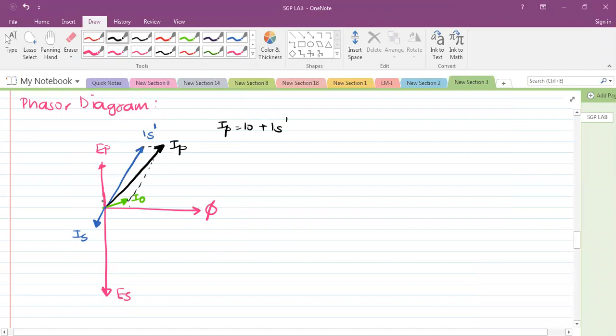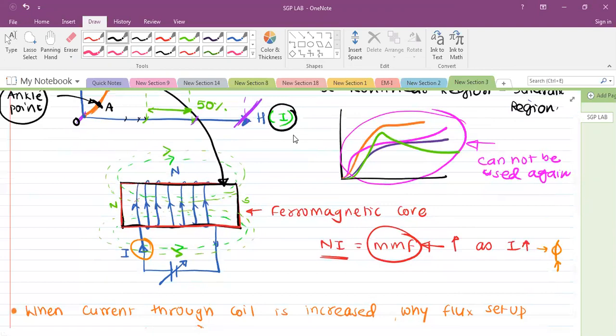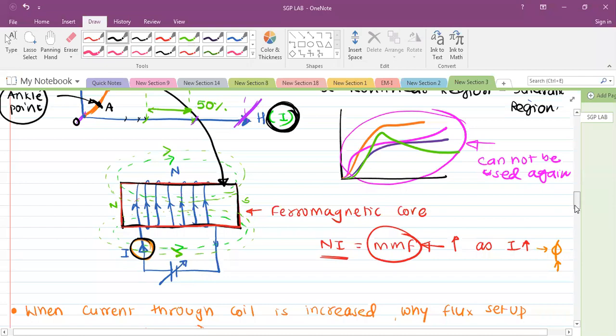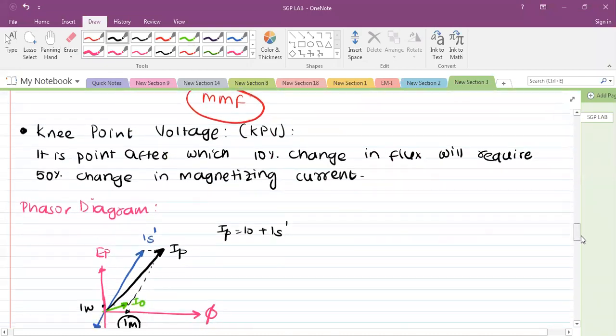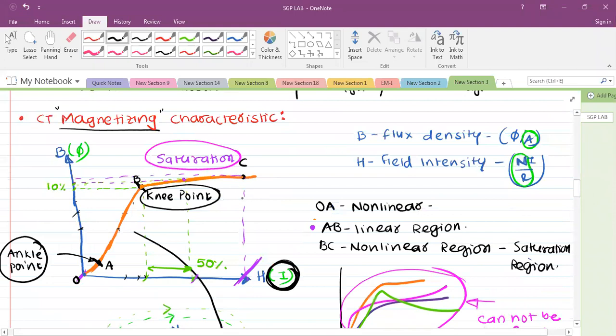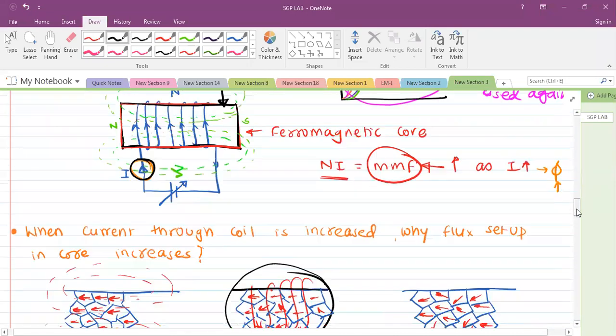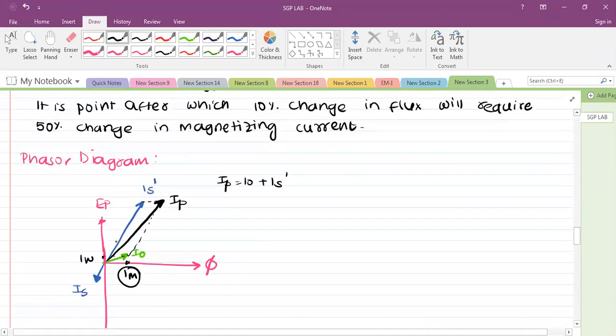And this I0 has two components, the magnetizing component and the working component, and right now we are discussing the magnetizing current, Iμ, which is generally 3 to 4% of the rated current. But if the machine goes into saturation, core, anything, we are talking about CT. So what will happen if CT saturates? If CT saturates, then the magnetizing current, which is very small, may become even more than the rated current. It may happen. Clear? Clear about this point?